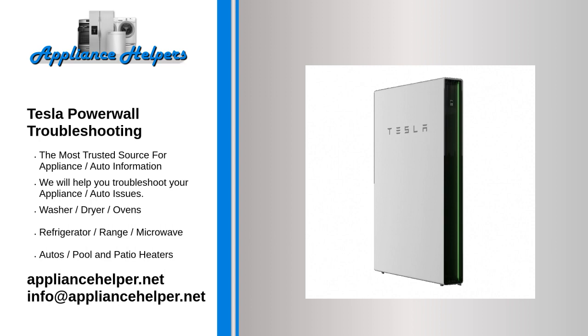Troubleshooting process. Step 1. Reset your gateway by pressing the reset button for approximately 10 seconds. Wait approximately 5 minutes for your Powerwall to reset. If your gateway does not have a reset button, or if resetting your gateway does not resolve your issue, proceed with the steps below. Step 2. Turn off your solar inverter if your home is connected to a solar system. Note: if you own a Tesla solar system, follow the steps to turn off your solar inverter. After selecting your inverter model, select Other as the error code, and then complete the first troubleshooting step by turning off the DC disconnect dial.